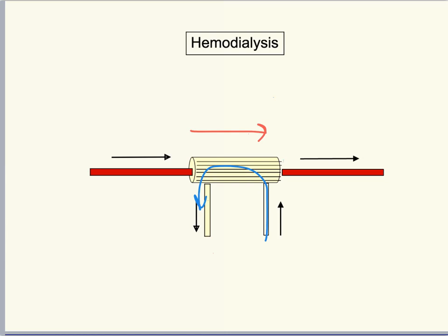In other words, if blood and dialysate traveled in the same direction down the dialyzer capillary, by the time the blood had traveled the length of the capillary, much of its urea and creatinine would have diffused into the dialysate so that the gradient for diffusion would not be nearly as good.